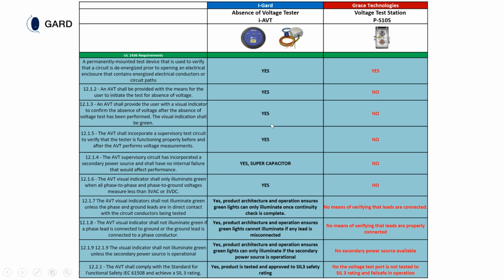When you've tested the system for the phase-to-phase voltage AC, phase-to-ground voltage AC, phase-to-phase voltage DC, phase-to-ground voltage DC, and you ensure that the continuity is continuous for the system, you get 3 green LEDs indicating that it is safe to enter that system. With the voltage test station, no, you cannot. The absence of voltage supervisory circuit has incorporated a secondary power source. Yes, we use a supercapacitor. There is no secondary power source on the test station.